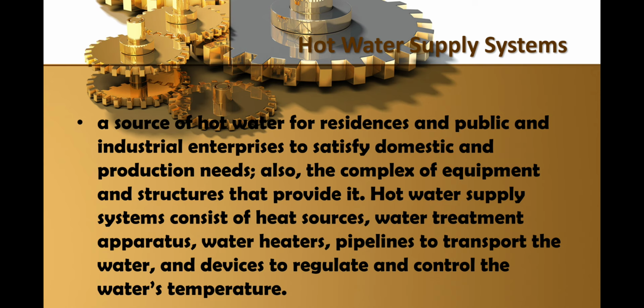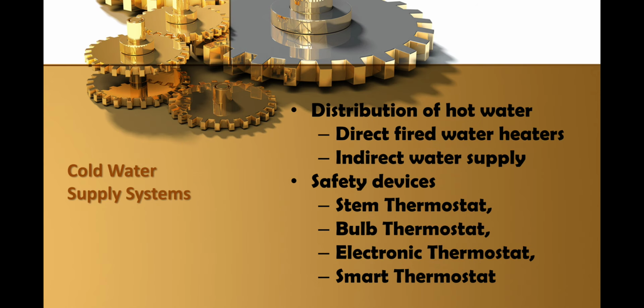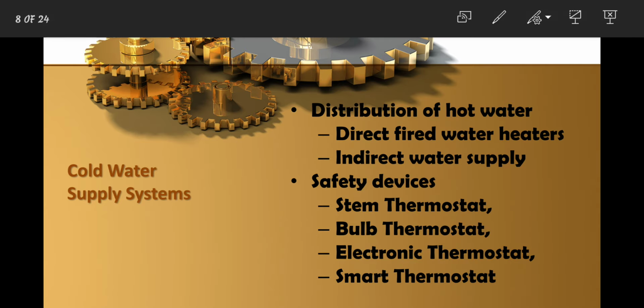The water provided by hot water supplies in residential and public buildings and in industrial enterprises for their operational daily needs must be potable. It can be heated by direct fired water heaters, which are solely dedicated to the job of hot water generation and provide a faster heat up and response time compared with an indirect system, which is in fact heating water to heat water. Because the only thing they do is generate hot water, they are more efficient than indirect hot water supply.